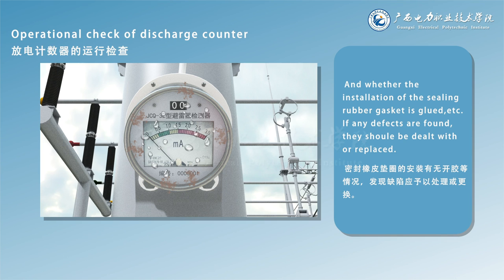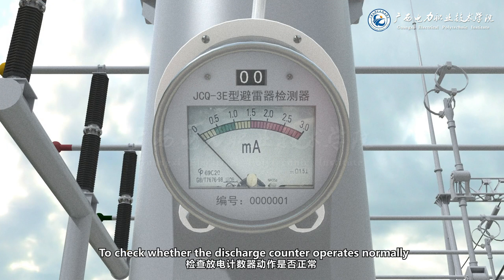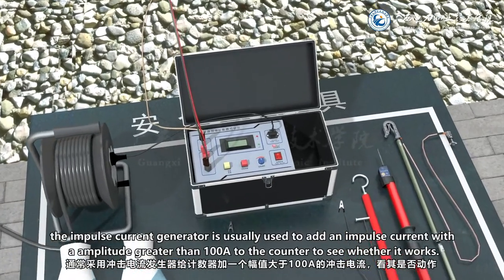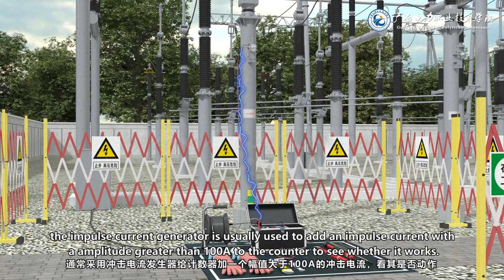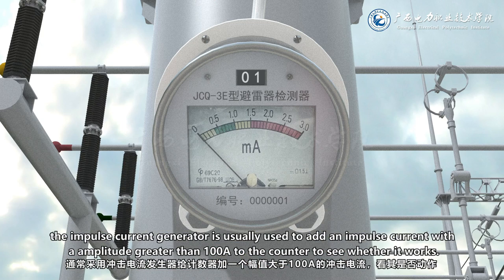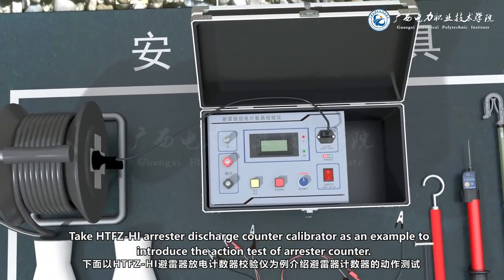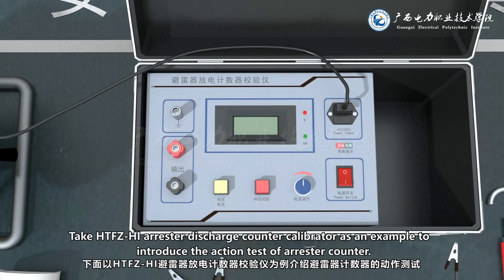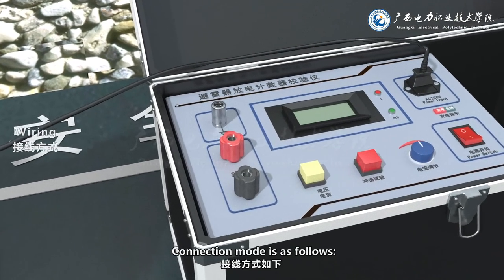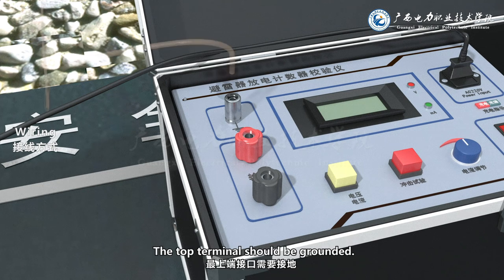To check whether the discharge counter operates normally, an impulse current generator is usually used to add an impulse current with an amplitude greater than 100 amperes to the counter to see whether it works. Taking the HTFZ-HI arrestor discharge counter calibrator as an example, the action test of the arrestor counter connection mode is as follows.